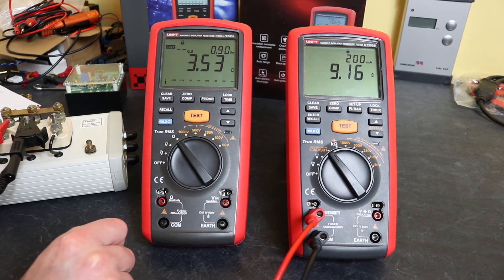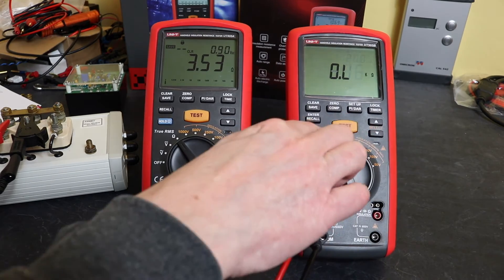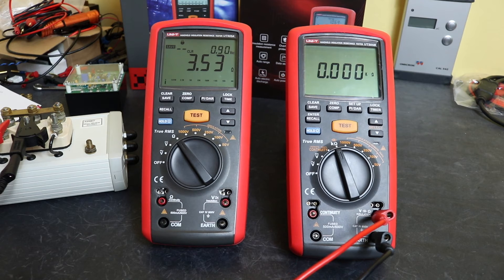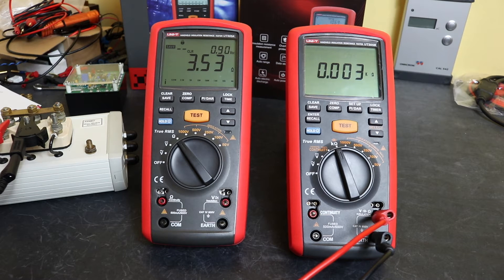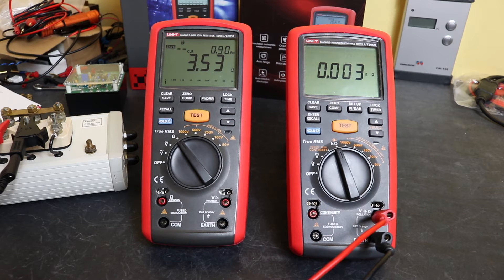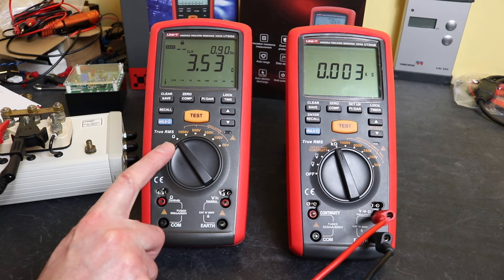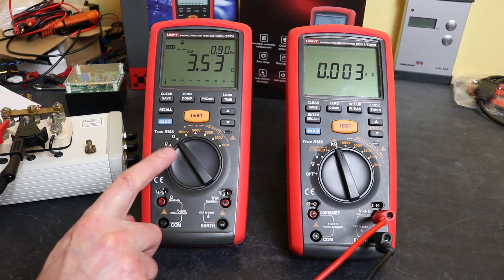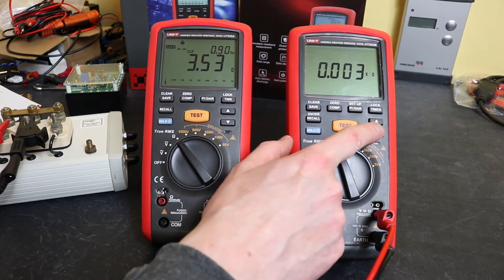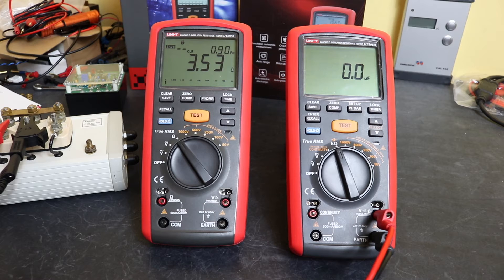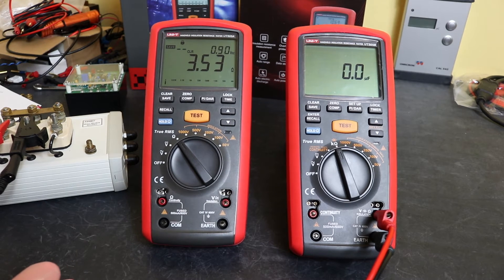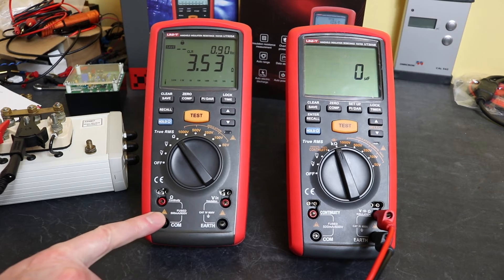With regard to the display layouts, you do get current on the UT505B whereas you display voltage on the UT505A, but it's still a 200 milliamp test function. On the UT505B it goes over to resistance and this will work fine - you can see we get 3 ohms there. In actual fact, on the UT505A although it only goes to 20 kilo ohms, it has a better accuracy specification than the UT505B does. However, moving on the same function switch, the UT505B does have a capacitance mode there as well that you don't see on the UT505A at all. That's the basic multimeter functions for each of the instruments.